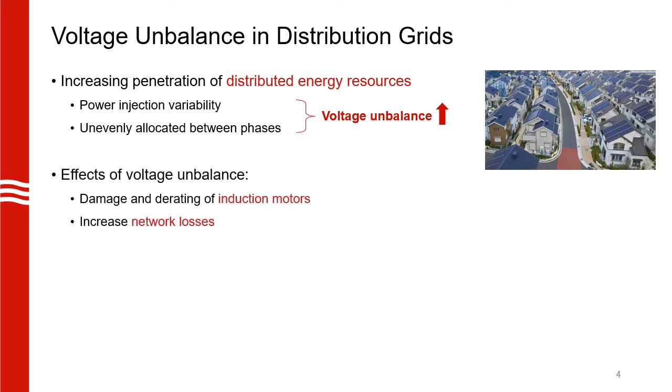In an unbalanced network, we have negative sequence components that affect three phase induction machines, which are by far the most commonly found loads in the grid and they are also very expensive. Additionally, we also have zero sequence currents flowing between the neutral connections and this can lead to increase in network losses.